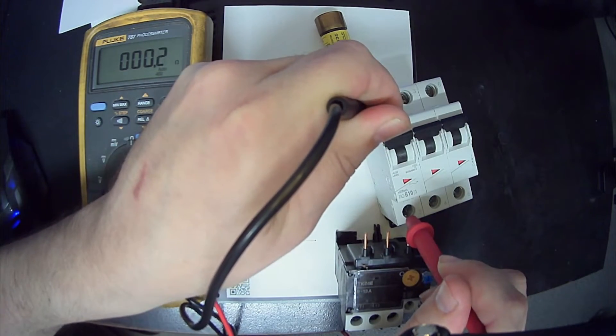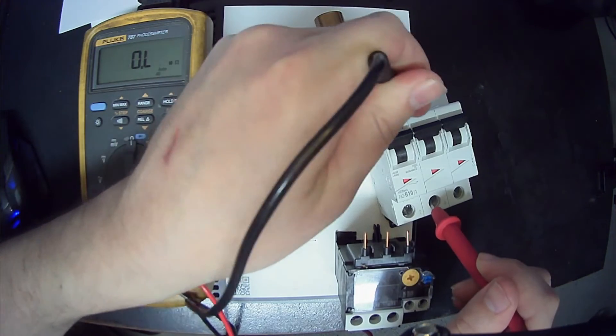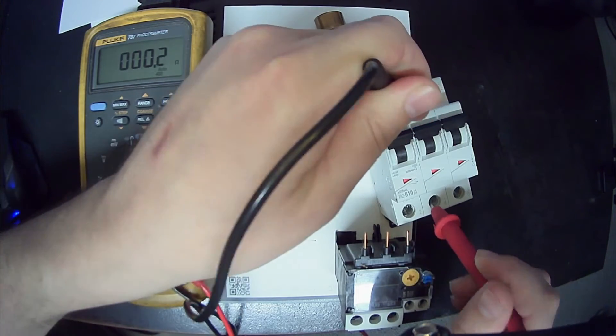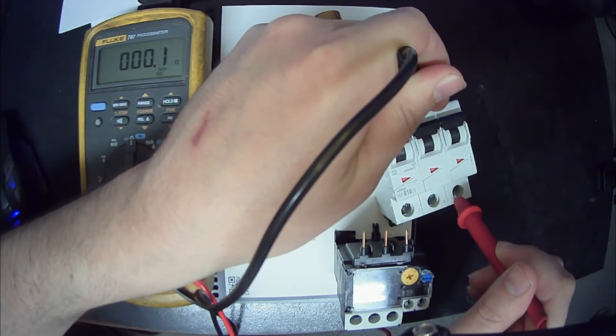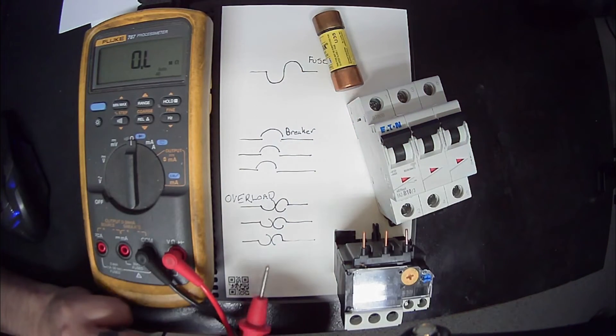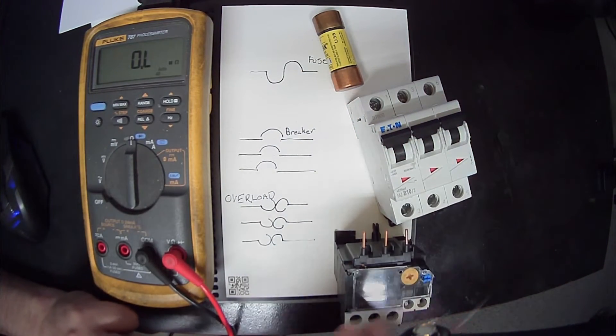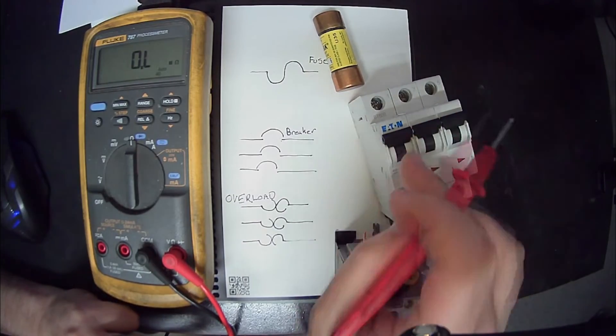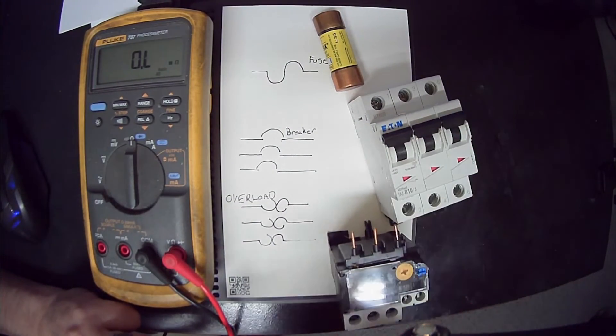I'm going to test across that, looking for very, very low resistance, and I'm going to check every single one across that and see that. Okay, that looks like a good breaker. That looks like a good breaker.